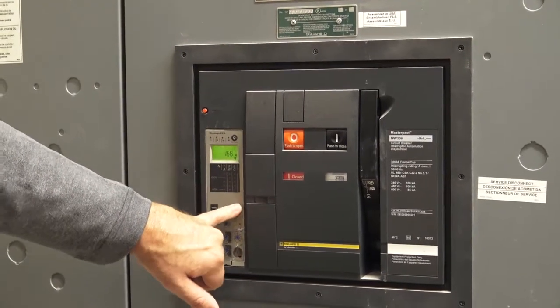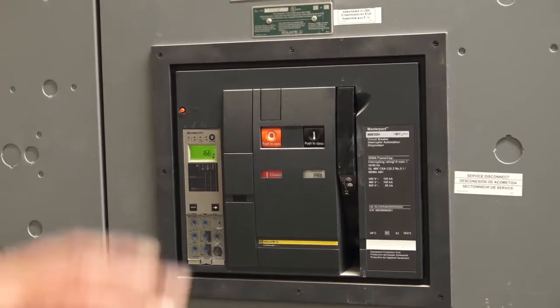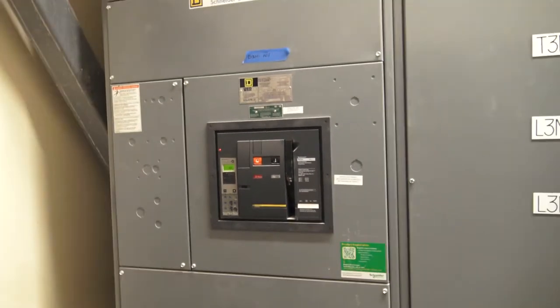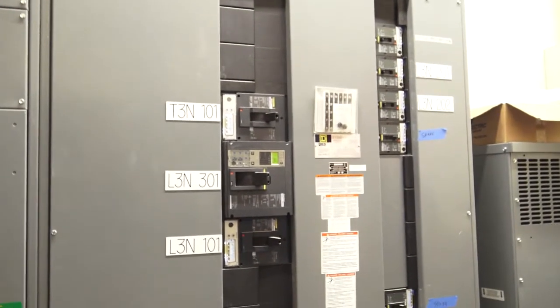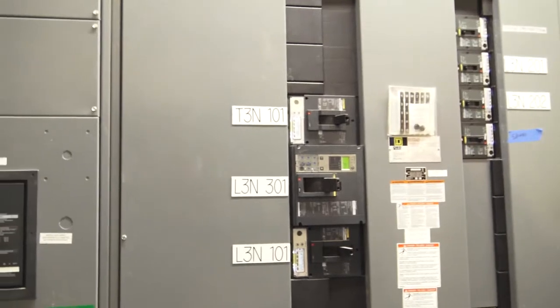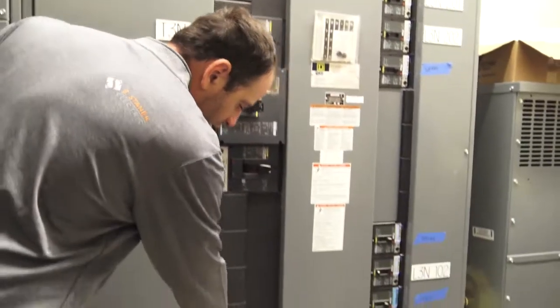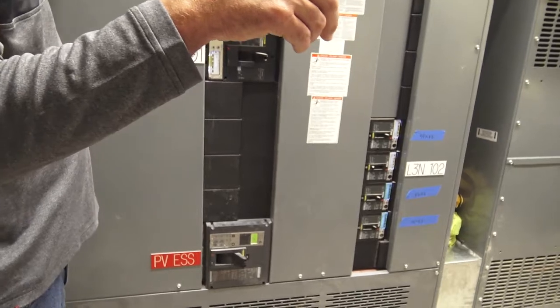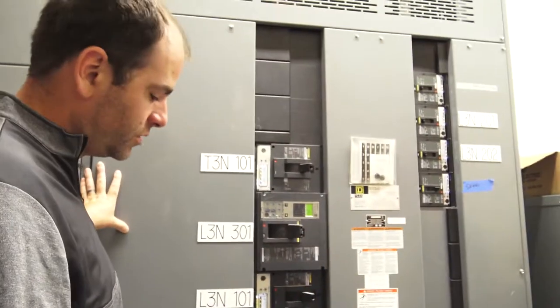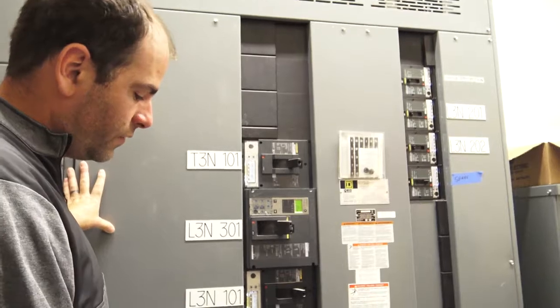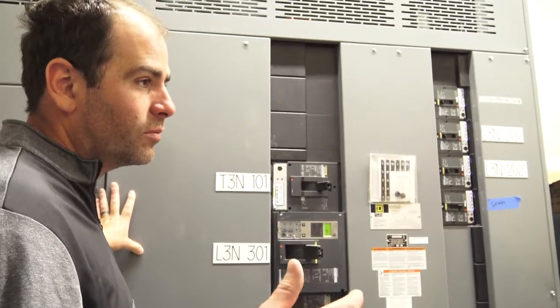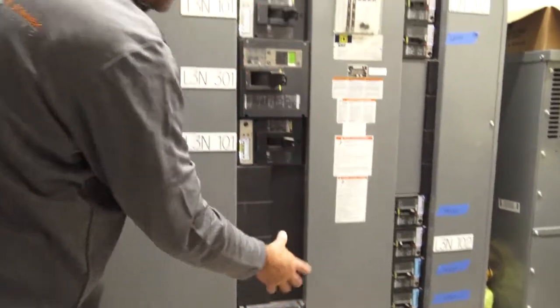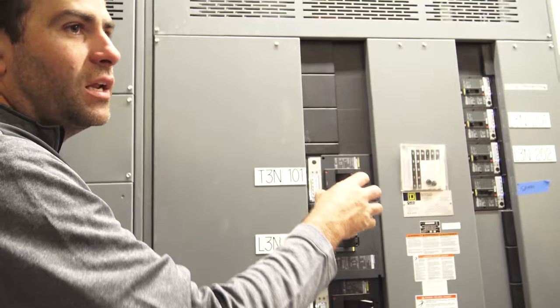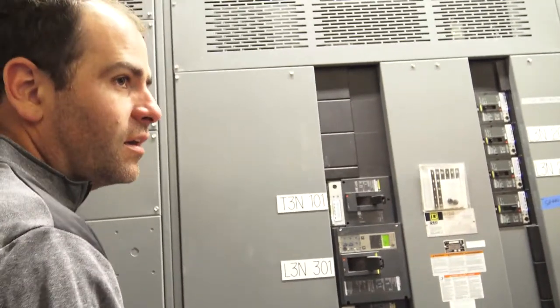But if you need to do that, pretty much all the breakers in here have basically the same setup. You can scroll through if you want to see the amp load on it. Once the solar gets working, this breaker feeds the panel, the emergency section, which is basically the battery panel. That will feed that section, and once you're producing power off the solar, it's going to come back into here, and then it'll feed every load in here. And if there's any remaining load coming off the solar, it's going to go back onto the grid.